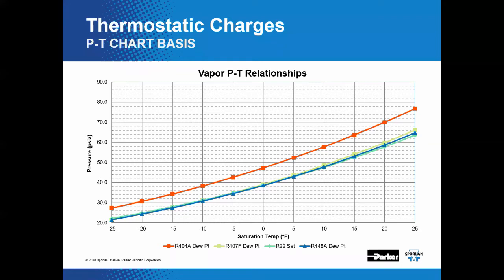That means that at a given coil outlet temperature, the R404A thermostatic charge will produce significantly more opening force on the pin than is needed. On some TEVs, there may be enough adjustment range and spring force available to overcome this. On others, there may not be. And when that's the case, you're probably going to need to change the TEV and we get to sell a new one to you.